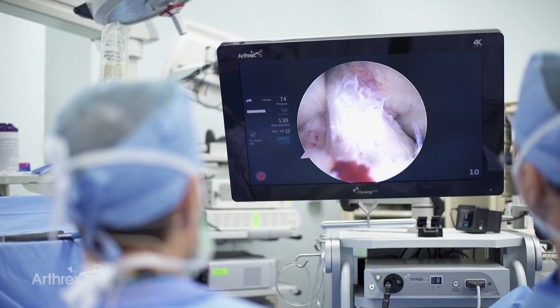Well, with a 4K system, the challenges for making an autoclavable system become even more significant. So to overcome those challenges, number one, we had to reconsider all of the optical design. And so the optical systems were completely reconsidered so as to optimize the image for 4K performance. Another significant challenge in making a 4K system autoclavable is that there's 4 times the number of pixels, and therefore the registration and precision of mounting these sensors relative to the optics is 4 times more critical. The processing challenge is now, again, 4 times as big. There's 4 times as much information. And lastly, not only does it have to function, it has to be ergonomically world-class.